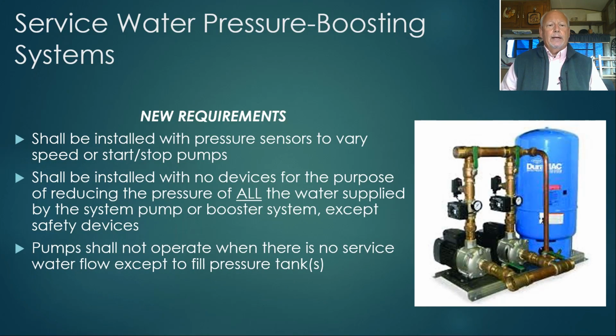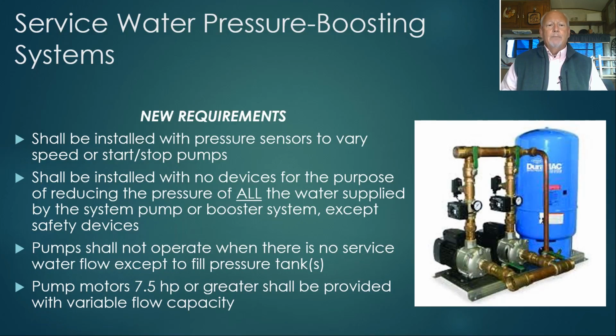Pumps shall not operate when there is no service water flow except to fill the pressure tanks. And finally, pump motors 7.5 horsepower or greater shall be provided with variable flow capacity. I think you would agree these are all good practice when it comes to service water pressure boosting systems, and now we've added that scope and that good practice to the Washington State Energy Code.